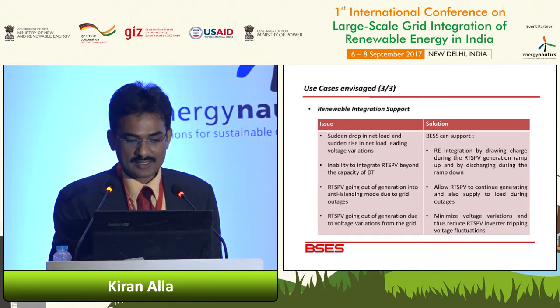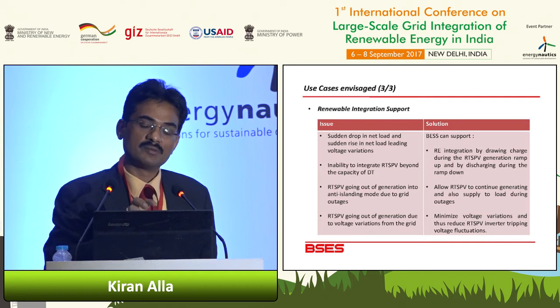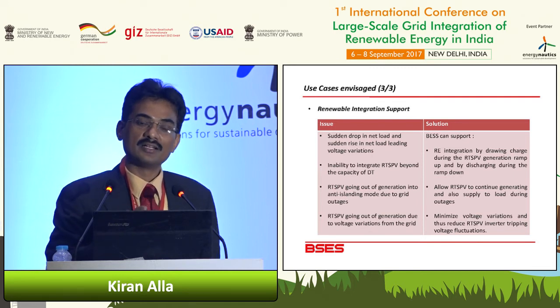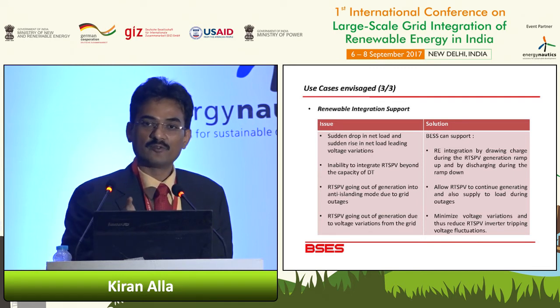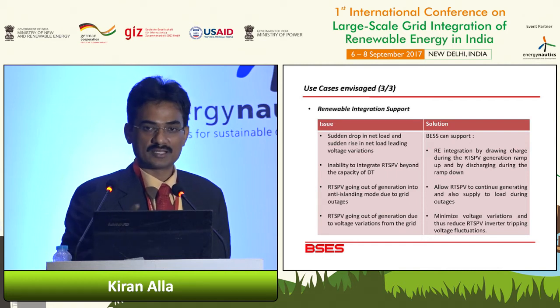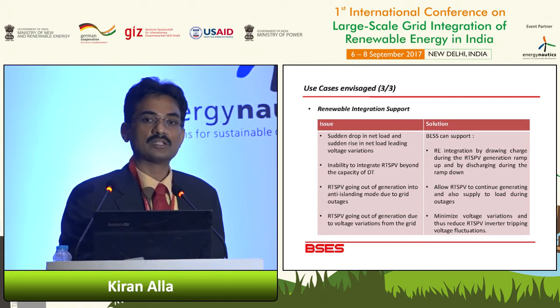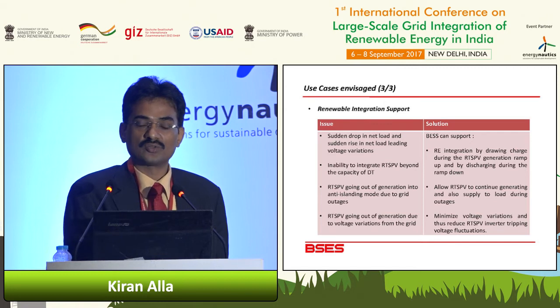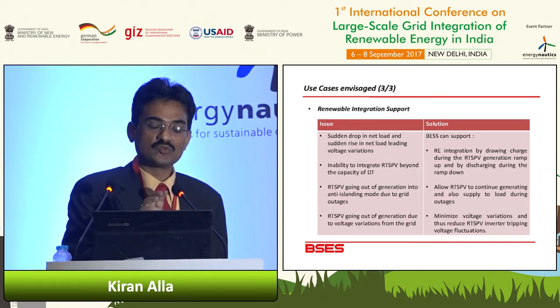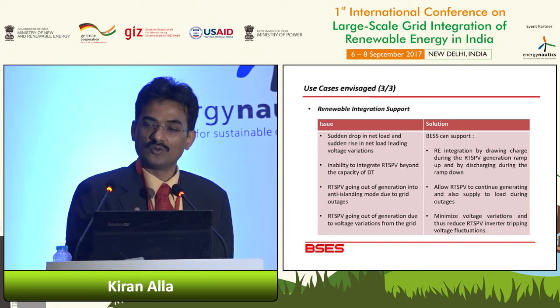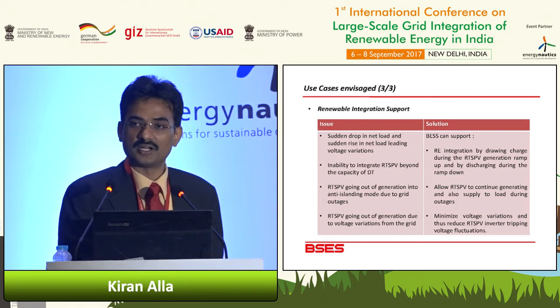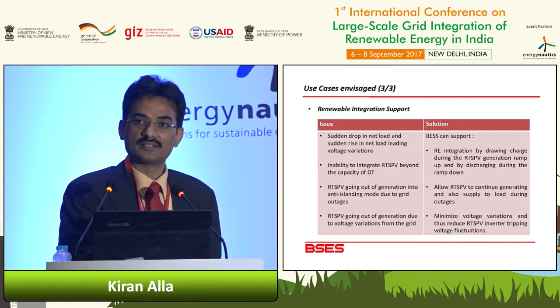With a microgrid, we can create an intended island, so generation never stops even during an outage. Similarly, voltage issues can be handled using the microgrid controller, so the inverter only faces issues within a certain band, keeping generation always on. This means we won't lose generation, while also getting other benefits using the battery system.